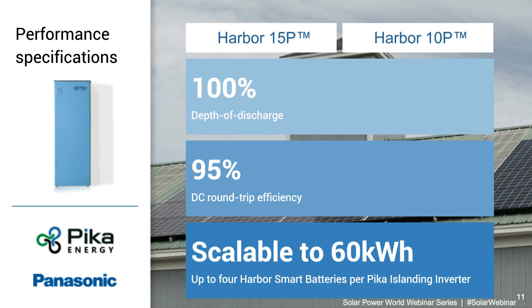And so both the 15P and the 10P models provide 100% depth of discharge. Again, the DC round trip efficiency of the system is about 95%. And with the batteries being connected on the DC bus and having a DC combiner built into the inverter, you can scale this up to as much as theoretically 60 kilowatt hours. And that would be a configuration that doesn't include PV, because you'd be using 4 of the 15 kilowatt hour batteries on the inverter, on all 4 of the breakers in the inverter.